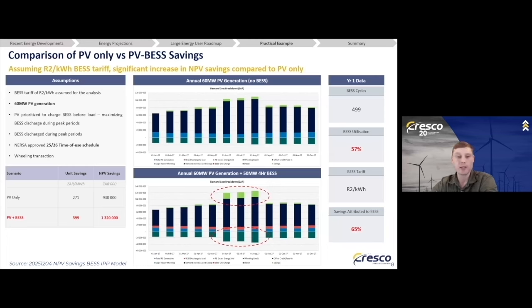And this is where the reduction in BESS capex really comes into play, where previously BESS only made sense when utilization was in the order of about 80 to 90%. The reduction in capex cost for BESS now has two consequences. So firstly, the BESS value is now driven by timing and not volume. And secondly, there's meaningful headroom for additional revenue streams.